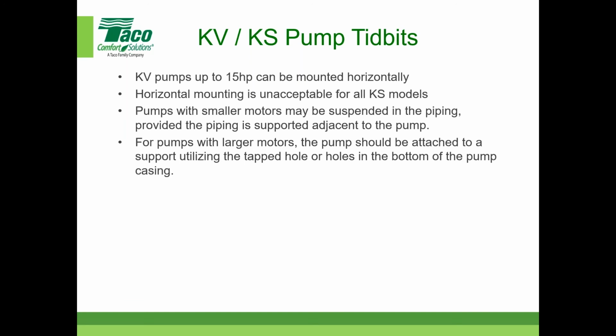With larger motors, maybe 20 horsepower is the cutoff from my perspective, though some people are more uneasy even at 15 horsepower, they should be attached to a support utilizing the tapped holes underneath or in the bottom of the pump. I'll show you some pictures of that shortly as well.